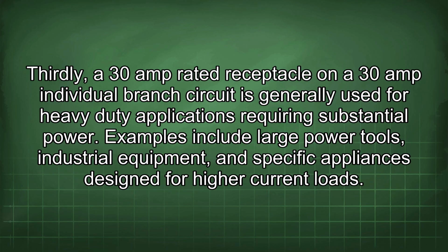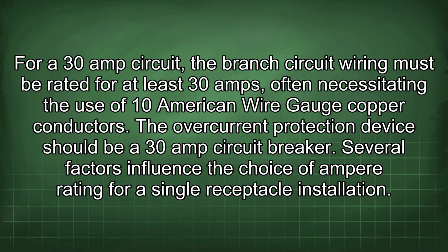Thirdly, a 30 amp rated receptacle on a 30 amp individual branch circuit is generally used for heavy-duty applications requiring substantial power. Examples include large power tools, industrial equipment, and specific appliances designed for higher current loads. For a 30 amp circuit, the branch circuit wiring must be rated for at least 30 amps, often necessitating the use of 10 American wire gauge copper conductors. The overcurrent protection device should be a 30 amp circuit breaker.